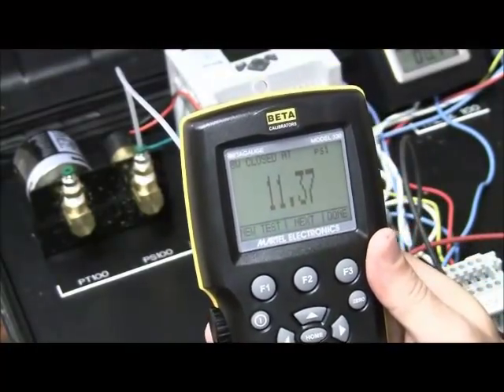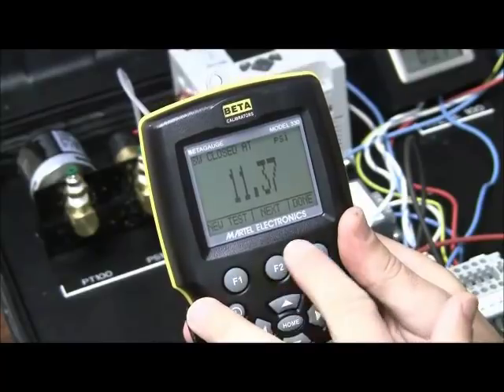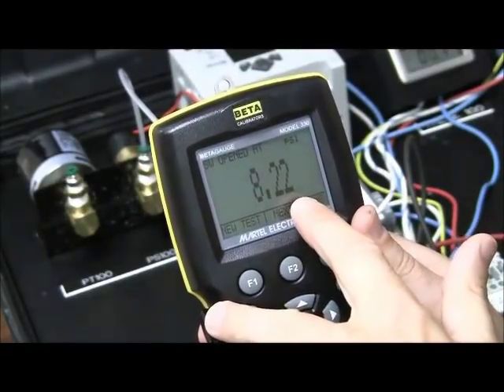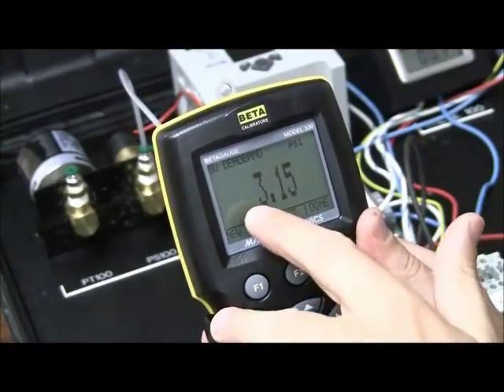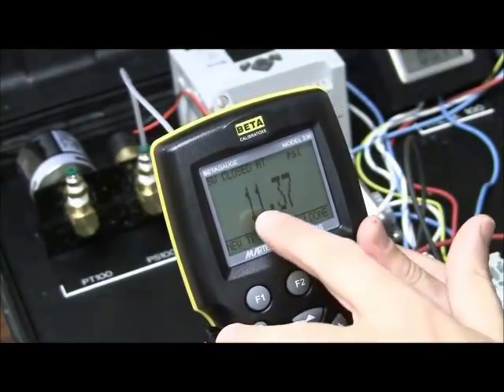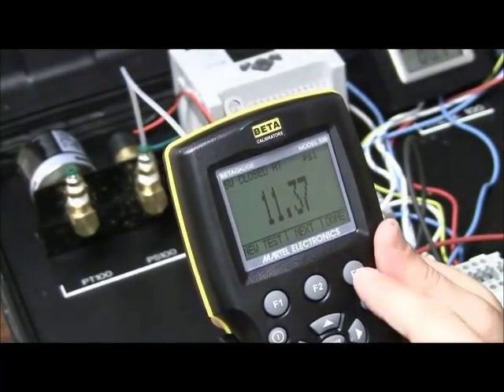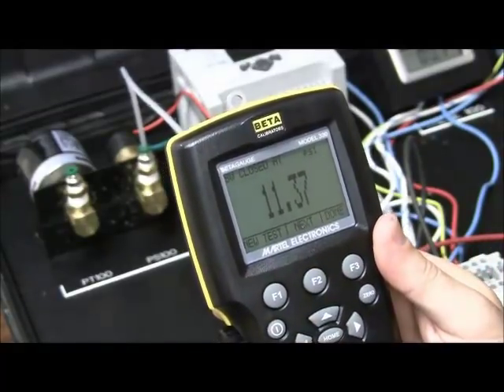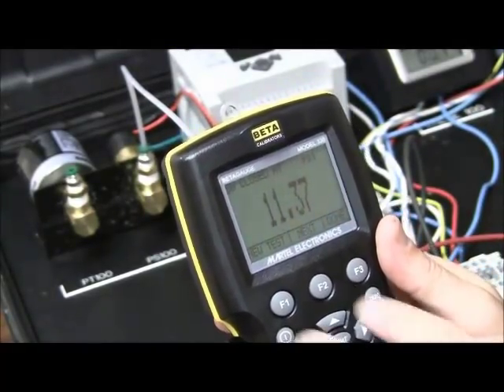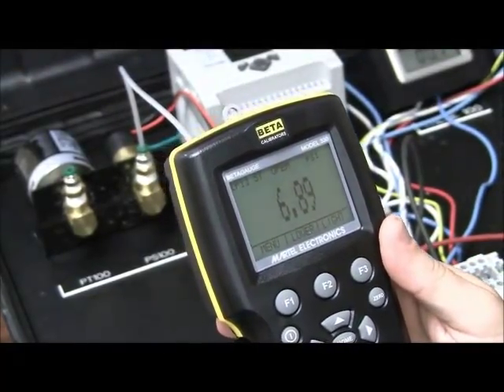Now, the test is done. And I can review this test here. I have the option at F1 to do a new test here. I can hit next. And I see that it opened at 8.22 PSI. I can hit next again. There's my dead band, 3.15 PSI. Hit next again. It closes at 11.37 PSI. Now like I said, I can hit done here. Or I can keep reviewing the results and document them on my pen or paper and do that. Or I can do a new test reel here and it starts you right back again to do the switch test.